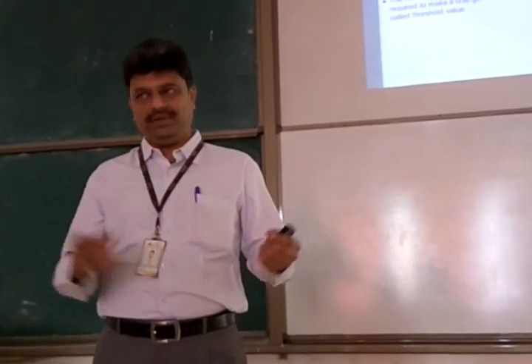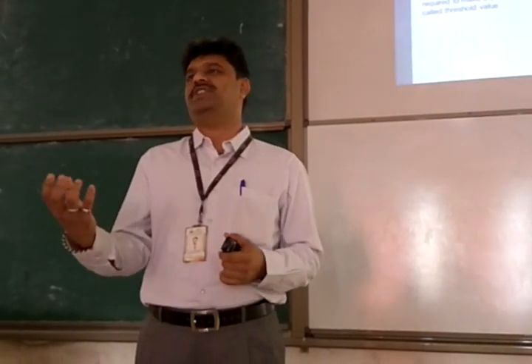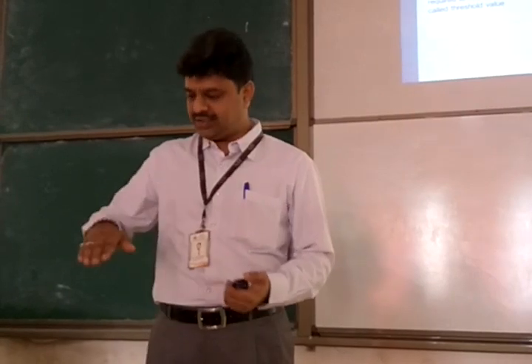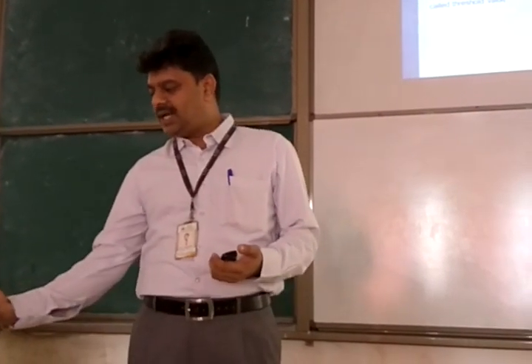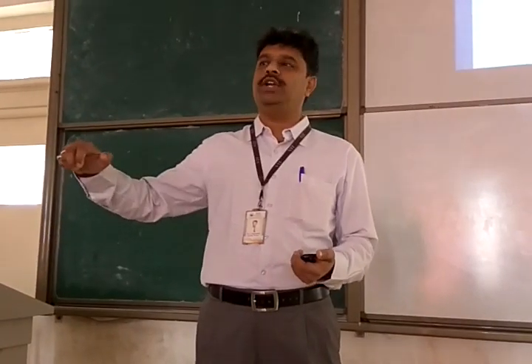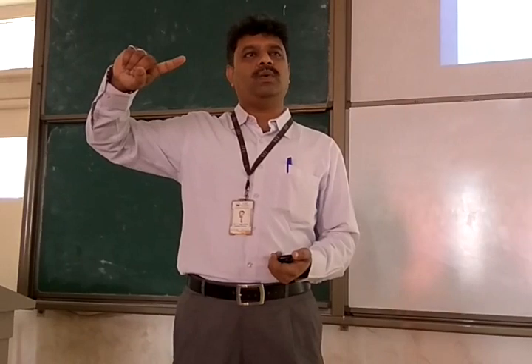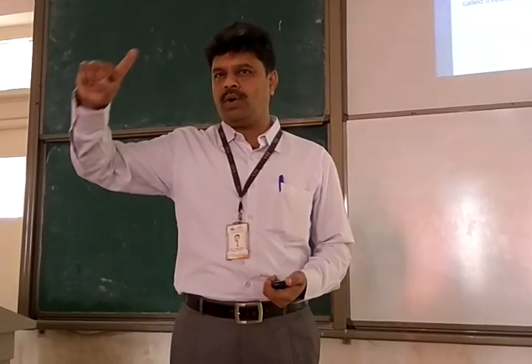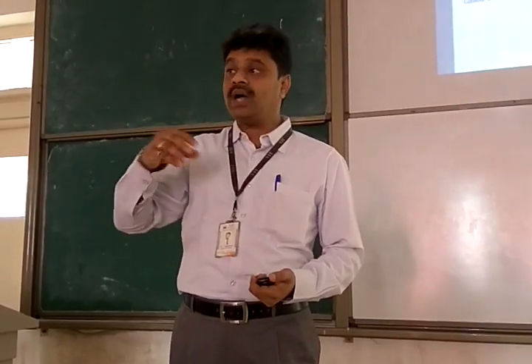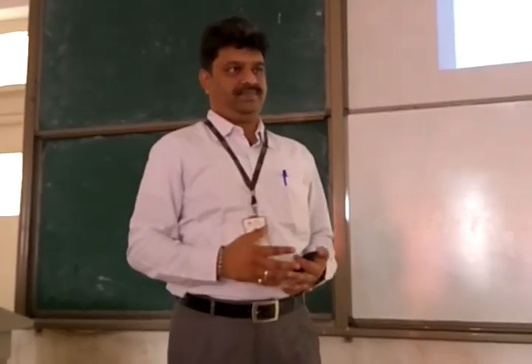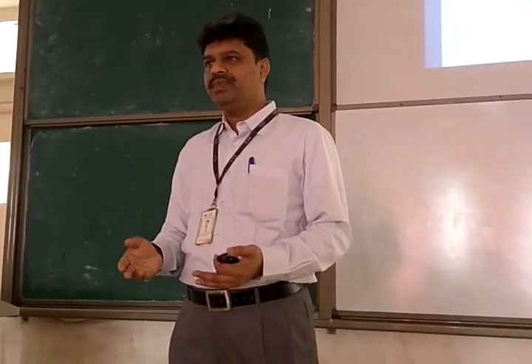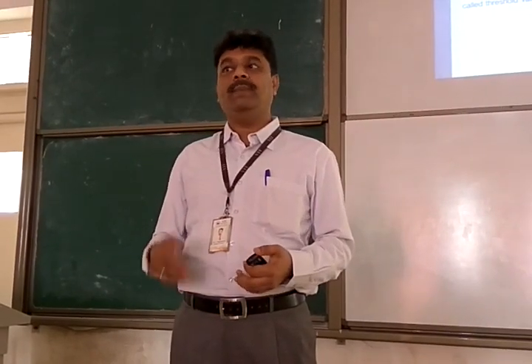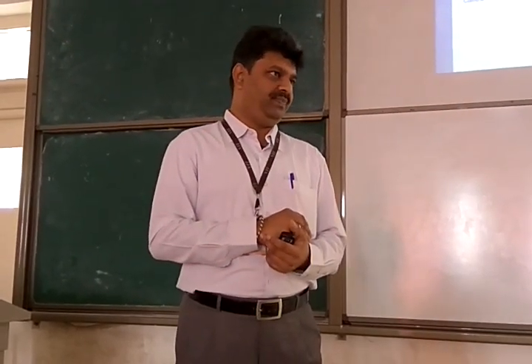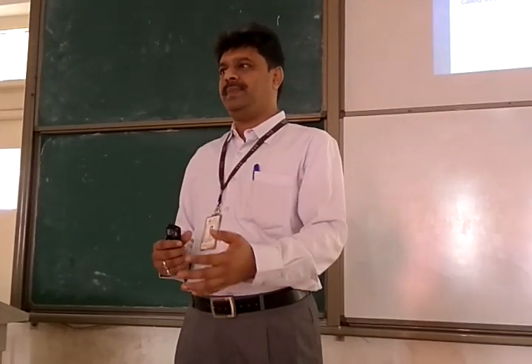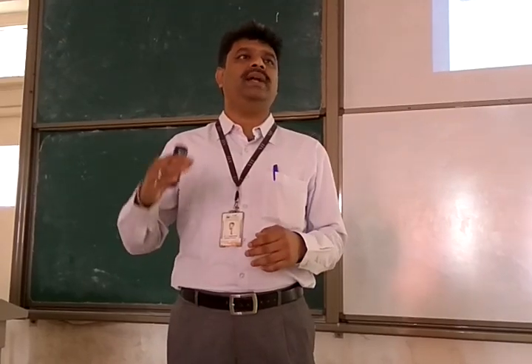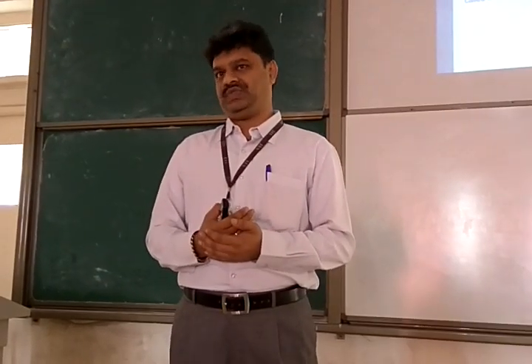For instance, yesterday some people used a Bourdon tube pressure gauge as part of pressure measurement. As you apply pressure with the pedal, the pressure builds in the cylinder, and there is a Bourdon tube pressure gauge that measures the pressure. Initially the pointer was at 0, and to move and show its first graduation, first reading, the amount of pressure that we have to give is called the threshold. Anything less than that threshold, maybe the instrument will be able to sense it, but we will not be able to make any meaningful measurement out of it. So threshold is the minimum value that we need to present to the instrument so that the instrument can produce a reading which is understandable by us. Alright.